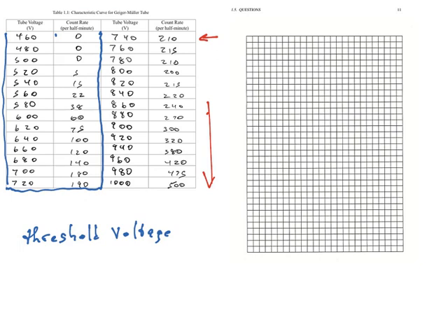But if you notice, in this region here, between the arrows, everything is about at 210. 210, 215, 200. And so that means for this range of values between 740 and 820, changing the voltage did not change the sensitivity of my equipment. What is this? This is operating voltage, or at least the region from which I can choose the operating voltage.